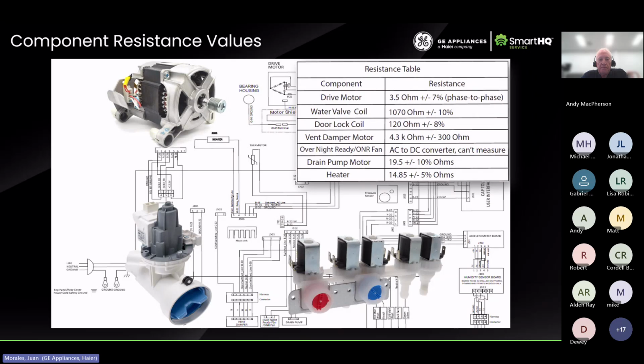But a lot of times you're not going to have the luxury of being able to move the unit at the point of installation, disassemble it, and get all the way to the component itself. So a lot of these times you want to measure directly from the main control board, which makes it easier. It also allows you to know if the wire harness is intact, because if you're measuring resistance from the component at the board, that means the wire harness is bringing the resistance all the way back to the main board, so the wire harness is more than likely in good shape.